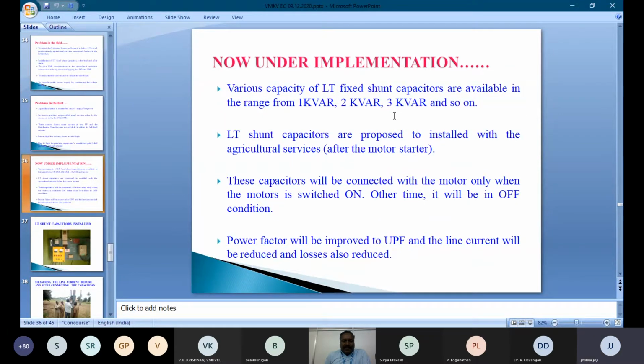Now, under implementation in our utility, LT fixed shunt capacitors of various capacities are available in the market, ranging from 1 kVAR, 2 kVAR, 3 kVAR and so on. It depends upon the requirement of the induction motor used in the agricultural sector. We can install 1 kVAR, 2 kVAR like this. This is one thumb rule: for a 3 HP motor, 1 kVAR is enough; for 5 HP, 2 kVAR is enough. For exact calculation, we can do the power factor calculation and the power factor correction also, but normally the thumb rule is okay. For 3 HP, 1 kVAR is enough. For 5 HP, 2 kVAR is enough. For 7.5 HP, 3 kVAR, and for 10 HP, 4 kVAR, and so on.